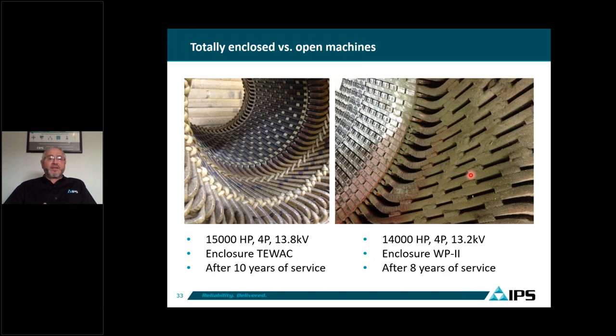Here is a comparison: on the left, a 15,000 horsepower totally enclosed water-air cooled motor after 10 years of service — the end winding looks very clean. On the right, a similar 14,000 horsepower four-pole, 13.2 kV WP2 motor after only 8 years of operation. You can see a lot of dirt and contamination on the end windings and some cooling vents starting to get clogged, which affects motor cooling. This customer changed their filters frequently but still shows significant contamination on the end winding.